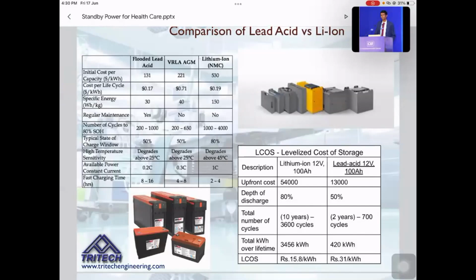Another very important thing is that the energy density of lithium-ion is somewhere around 5 times that of lead-acid, which means it occupies that much less space. So if you look at any institution where space is a constraint, this will be the number one priority. So apart from the lower cost of ownership for lithium-ion, these are the parameters you need to consider when you're looking at the type of batteries. At this point of time, lead-acid is a cheaper alternative, but lithium-ion is still an excellent option if you have the extra initial money to spend.